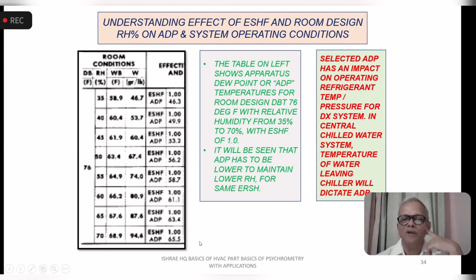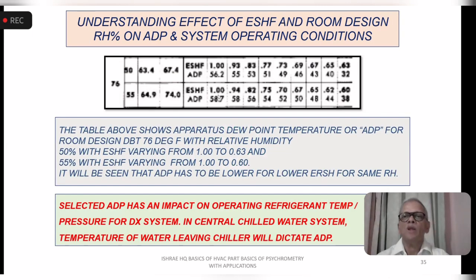So this is a sample with the effective sensible heat factor as one. What is the effect of changing the design relative humidity? Now let's see the other part: the effect of a change in the effective sensible heat factor for the given humidity. This is showing 76 degrees Fahrenheit dry bulb temperature with 50 and 55% RH, and effective sensible heat factor changing from 1 to 0.63 or 0.6.